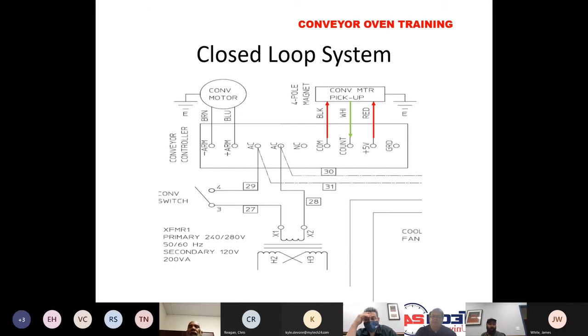As we look at this, at the bottom of it, you can see that we have a transformer and we have two leads that are going to our AC. This AC voltage is the input voltage to our controller. At the top left, we have an arm plus and arm minus. This is the DC voltage out to our conveyor motor. And then over here to the top right, we have a 4-pole magnet that is being sensed by our pickup. There are 3 terminals for the pickup. One is common, the second is +5. When we look between common and +5, we're going to see 5 volts DC. When we look between common and count, we're typically going to see about half of that voltage, or about 2.5.